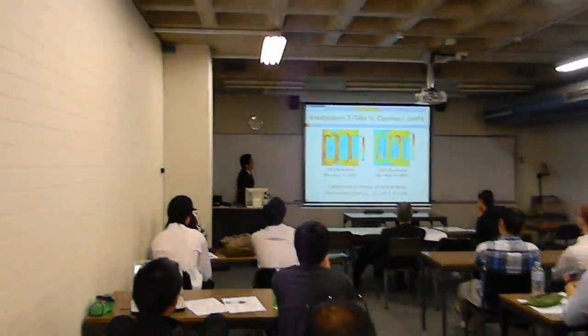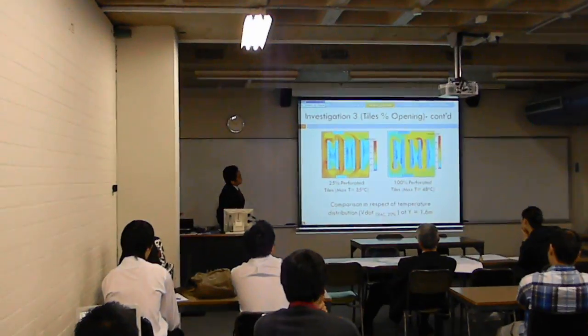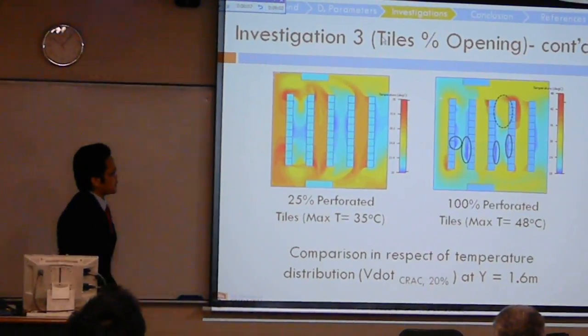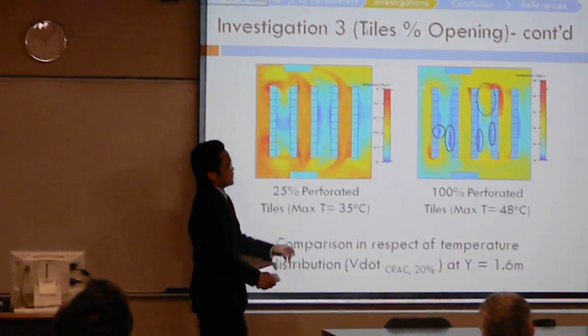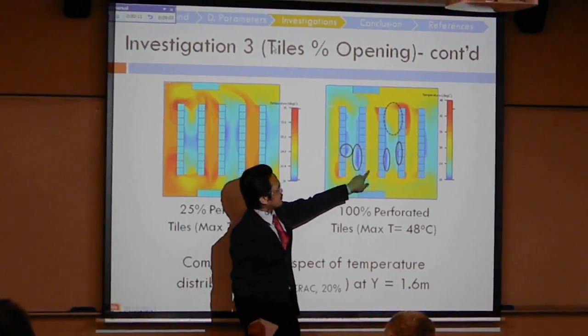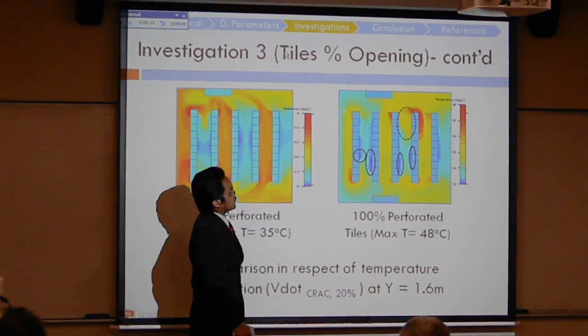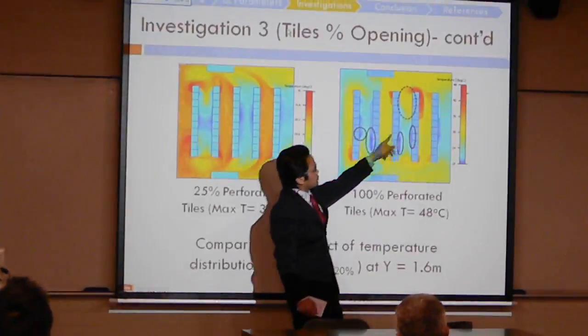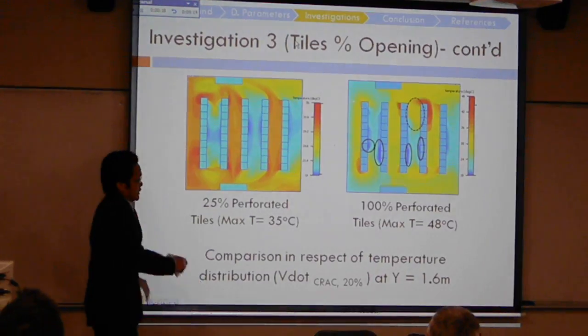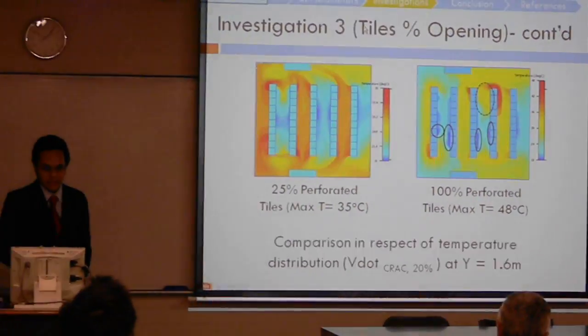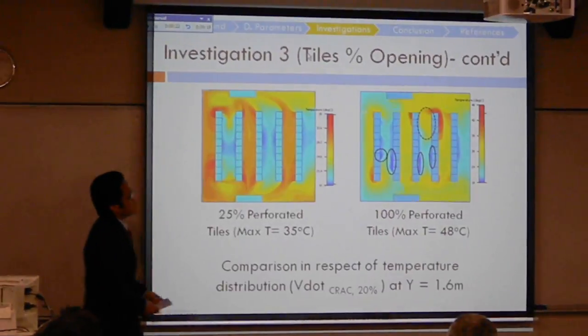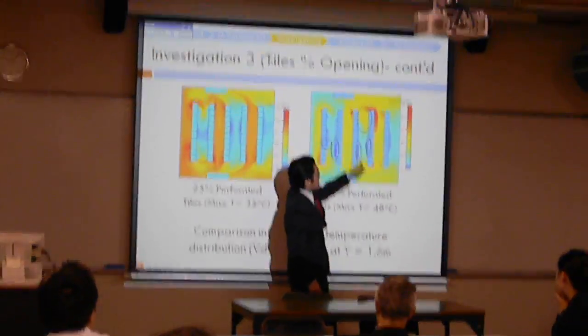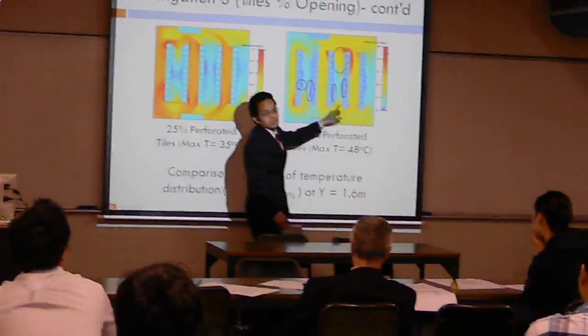If you look at the temperature distribution that came from the top of the center, there will be few regions that will be super cool. This region will be very, very cool. And eventually we lead up to this dashed oval — it is the region that is very much deprived of the cooling net. Due to that, hot air infiltration will occur at this particular region and disturb the whole entire function of the cold aisle.